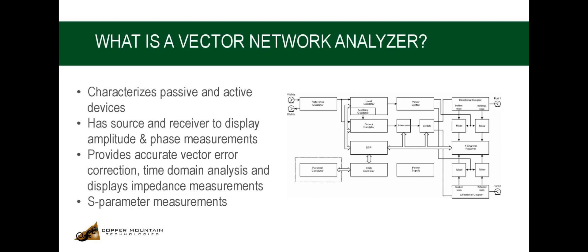To perform these measurements, the analyzer supplies the source signal of the assigned frequency from one of the ports to the DUT and then measures magnitude and phase of the signals transmitted and reflected by the DUT and finally compares the results to the magnitude and phase of the source signal.